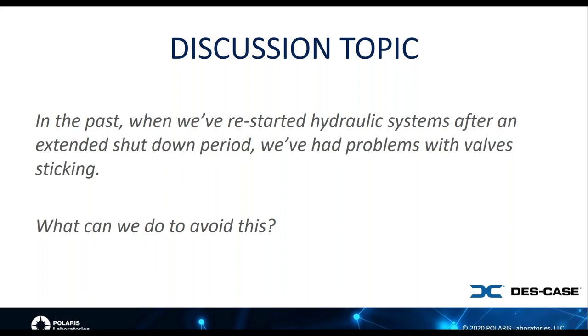And what happens is those varnish particles will actually get trapped within small clearances where the oil is static. And of course, when the machine is shut down and the oil is not flowing, that oil will sit stationary. Varnish byproducts are actually temperature dependent in terms of their solubility. So while the machine is running and the oil is warm, those deposits and byproducts of oxidation are sometimes dissolved in the oil and don't create as much of a problem.